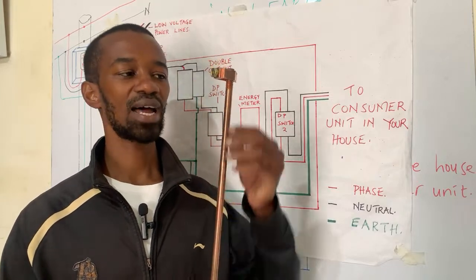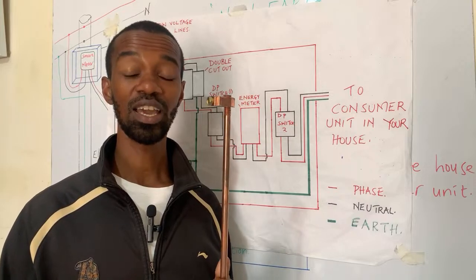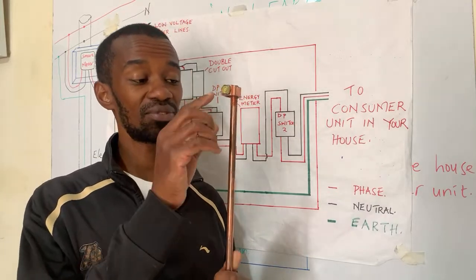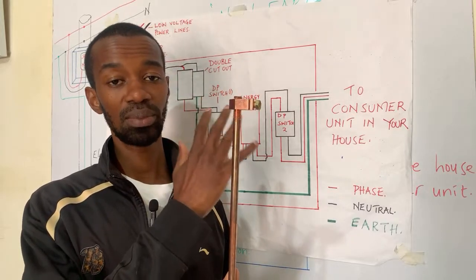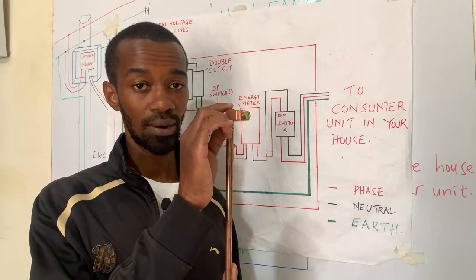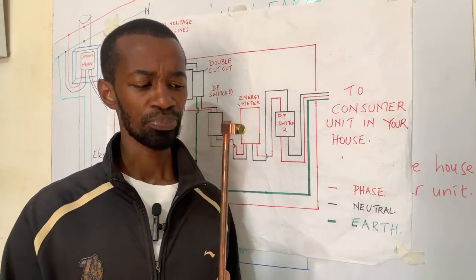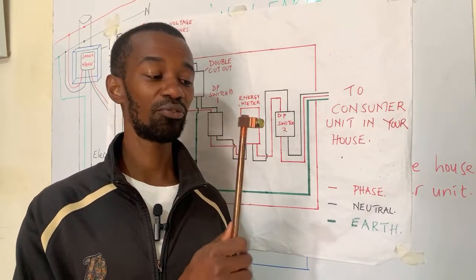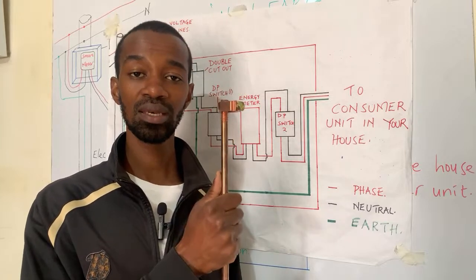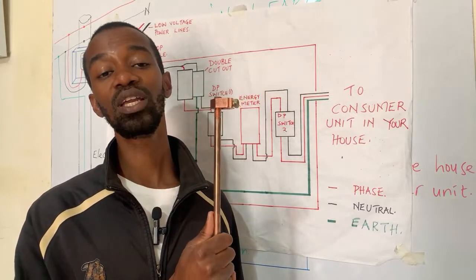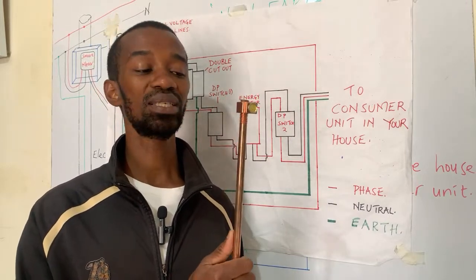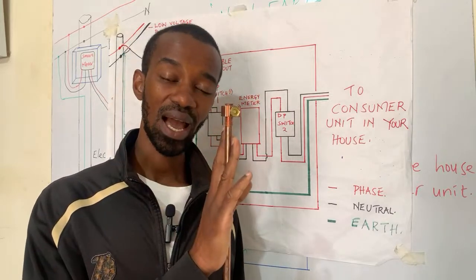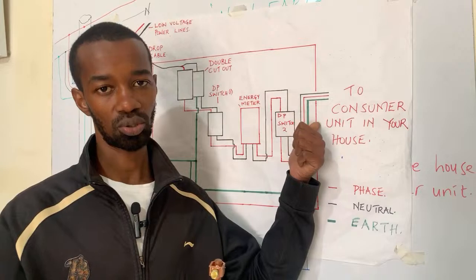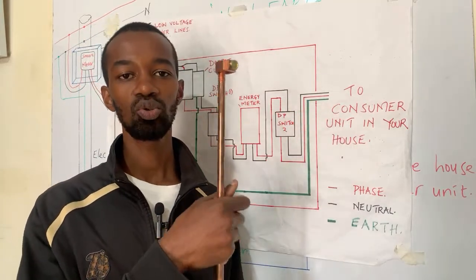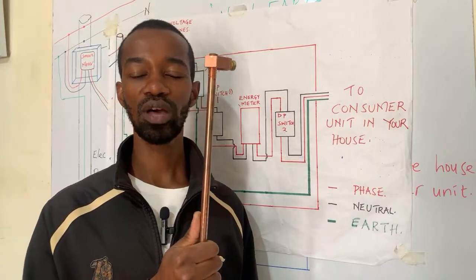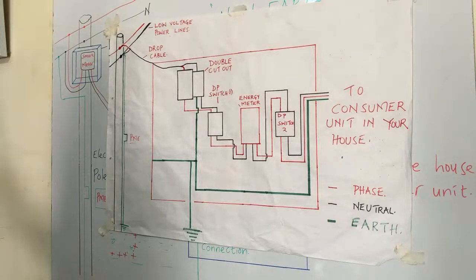You cannot just have an earth rod in the earth and assume that everything is okay, because the excessive charges that will flow from the meter box or the meter board to this earth rod must find their way to the ground also. If the ground is not conducive for the charges to find their way back to the transformer, it means that there will be a very huge resistance. And those charges may still stick to the earth rod, to the earth connection, and even to the installation. So you must ensure that that path to the ground is smooth and without, or with very minimal, resistance.